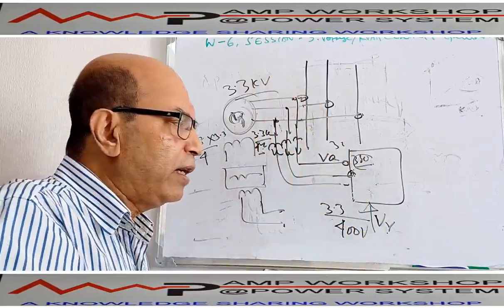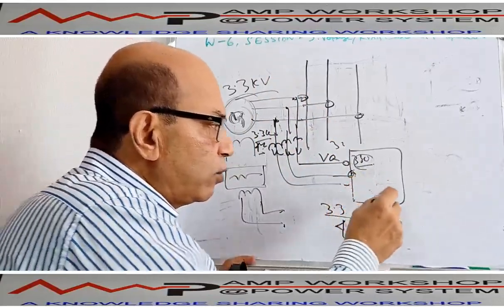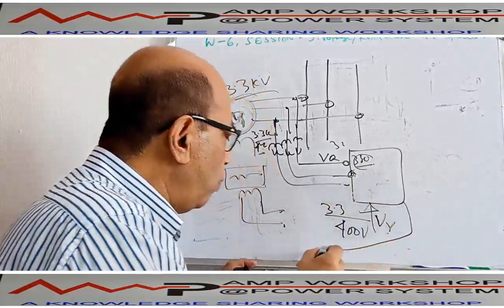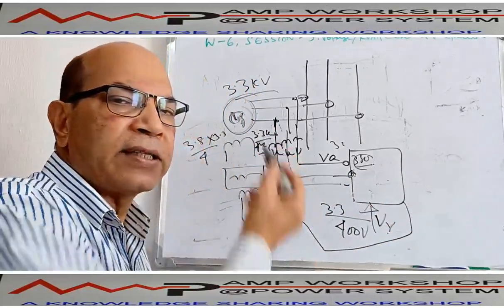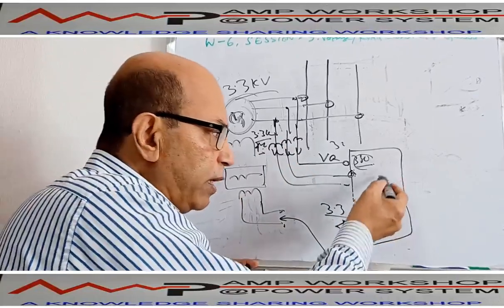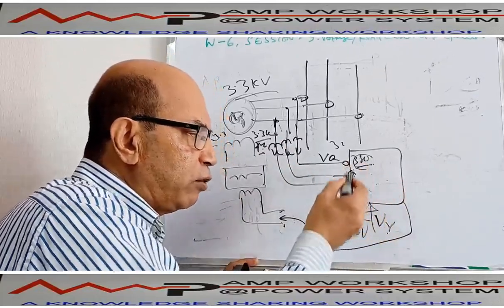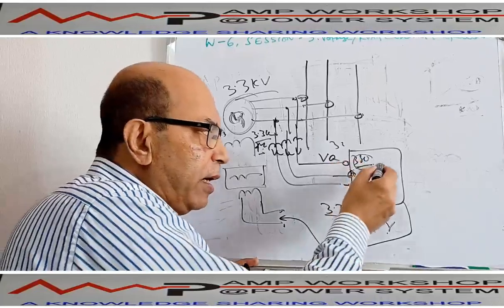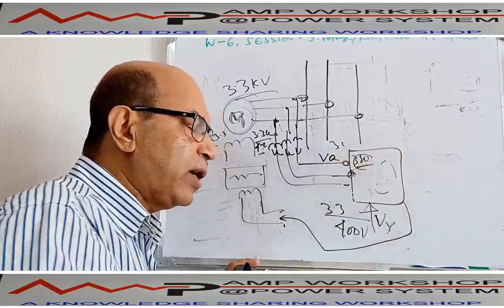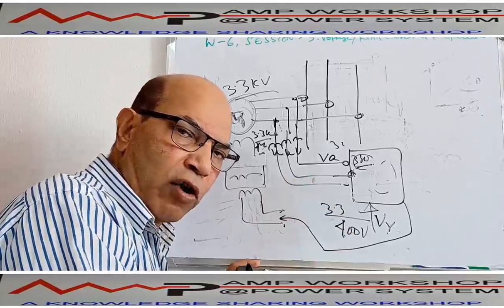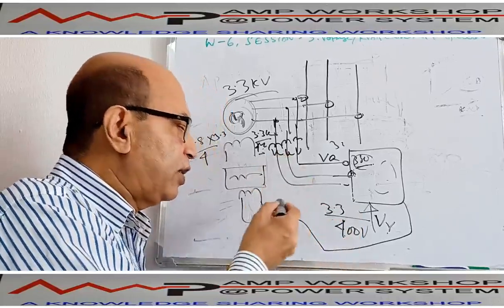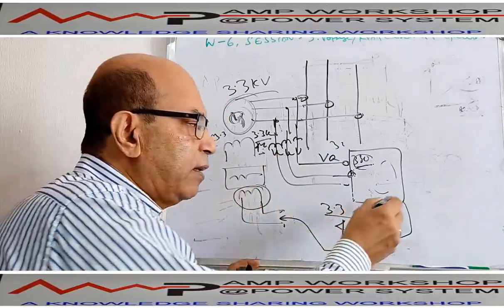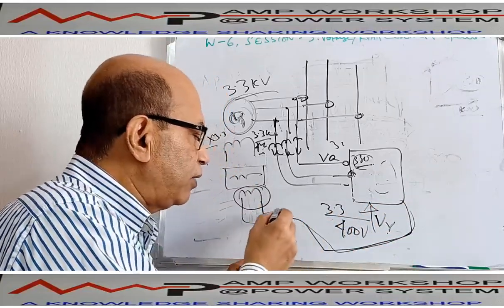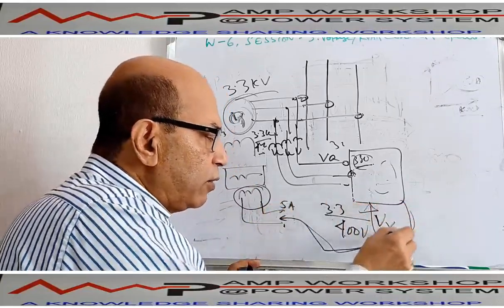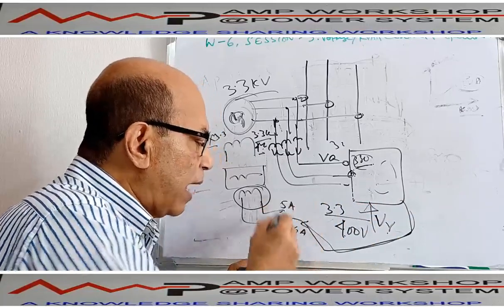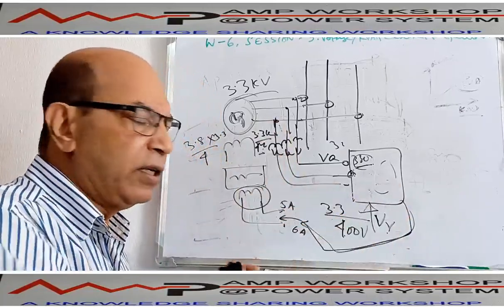rectify this. When the difference is coming, what does it have to do? It has to give an output signal to whom? To this exciter, to increase the excitation. The moment it sees the actual voltage is lower than the reference voltage, this device will understand that there is a drop of voltage, so we have to increase the excitation, means the exciter rotor field excitation. So it will give some more DC current. Suppose 5 ampere current is flowing, now it knows I have to increase the current to 6 ampere. So accordingly it will increase the current. How we do that, we'll discuss this part.